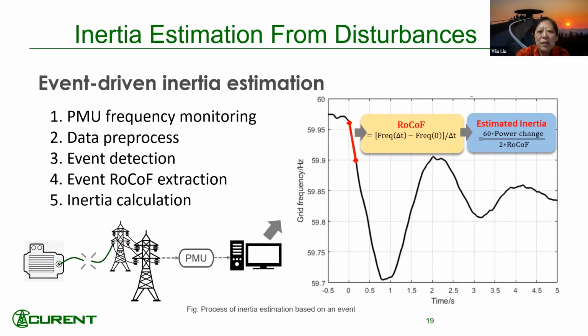If you look at the curve on the right, this is a generation trip, and usually there's some kind of oscillation that goes with it. The slope of this trip, the red part, is a function of how big a generator tripped, as well as how big the system inertia is. If I somehow figure out which generator tripped, and NERC always, whenever they confirm the trip, they come back to us and tell us which trip it was, where, and at what megawatt. So I know the trip amount, not in real time, but after the fact. And then I know the system inertia.